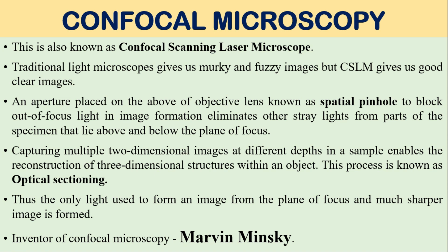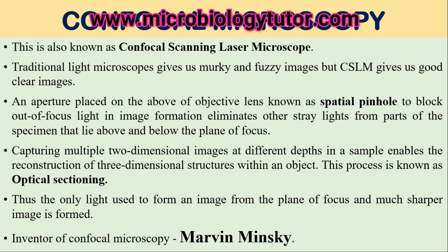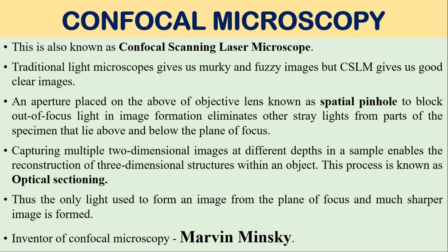CSLM, or confocal scanning laser microscope, gives us a good and clear image. Here, an aperture placed above the objective lenses is known as a spatial pinhole. The purpose of the spatial pinhole is to block out-of-focus light in the image and eliminate other stray lights from parts of the specimen that lie above and below the plane of focus. Capturing multiple two-dimensional images at different depths in a sample enables the reconstruction of three-dimensional structures — a process known as optical sectioning.